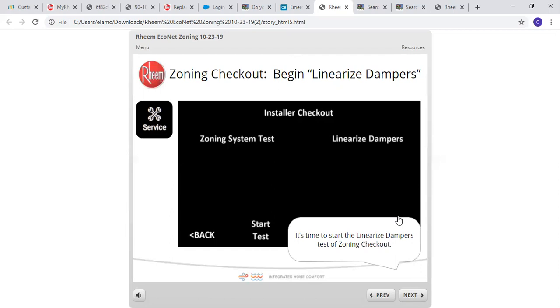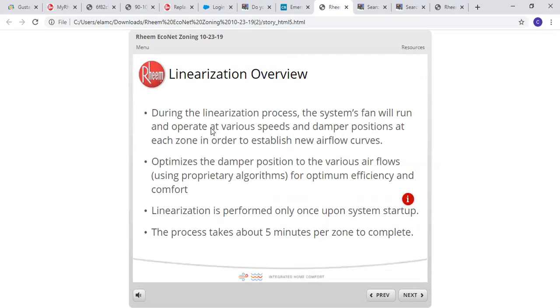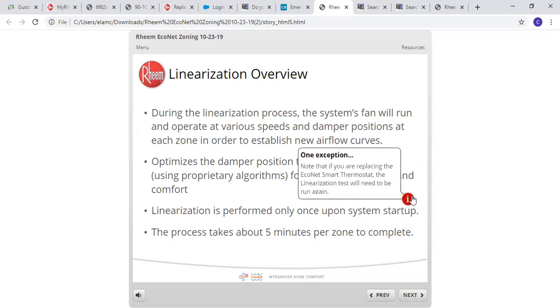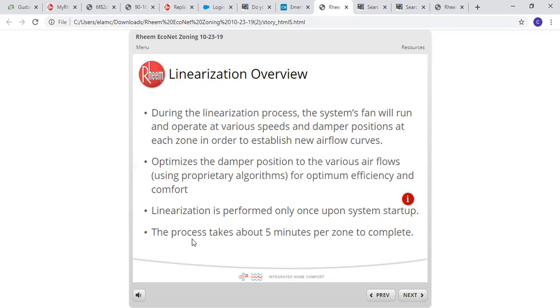Okay, so at that point, we're going to go on to the linearization of the dampers section. So we're going to go to linearization. During the linearization process, the system's fan will run and operate at various speeds. The damper positions at each zone establish new airflow curves. This will optimize the damper position to the various airflows using proprietary algorithms for optimum efficiency and comfort. Linearization is performed only once upon system startup. One exception: if you're replacing the Econet smart thermostat, the linearization test will need to be run again. And this process can take up to 5 minutes per zone to complete.